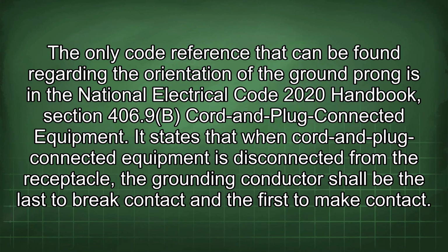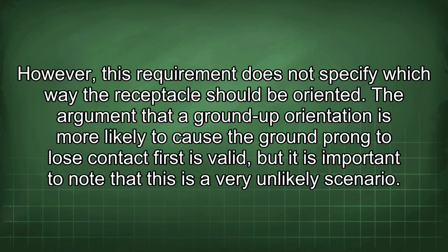The only code reference that can be found regarding the orientation of the ground prong is in the National Electrical Code 2020 Handbook, Section 406.9b, Cord and Plug Connected Equipment. It states that when cord and plug connected equipment is disconnected from the receptacle, the grounding conductor shall be the last to break contact and the first to make contact. However, this requirement does not specify which way the receptacle should be oriented.